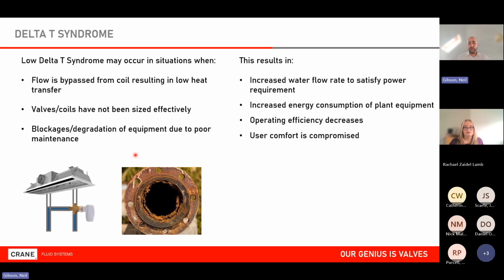Something was happening that it couldn't dissipate the heat. There could be multiple reasons for this. Poorly designed system is usually the main one, but poorly maintained systems as well. We could have systems which aren't installed correctly, so bypasses are open, so the heat just isn't dissipating.